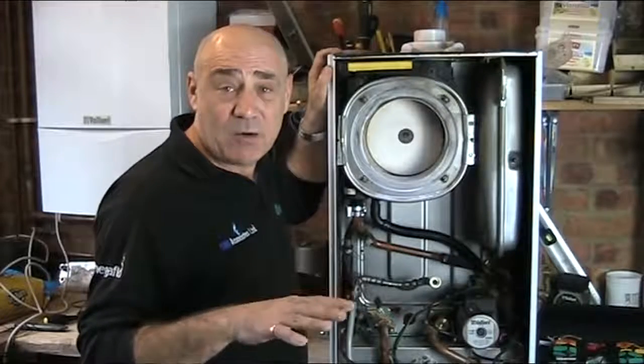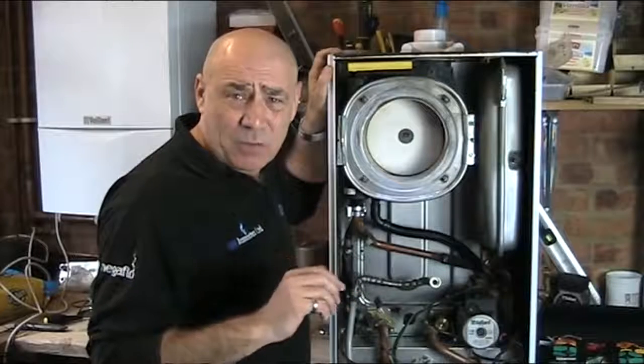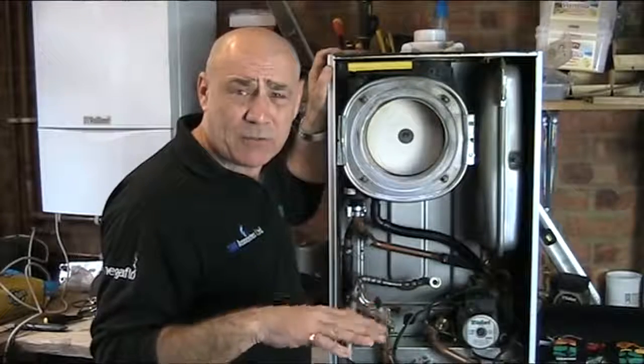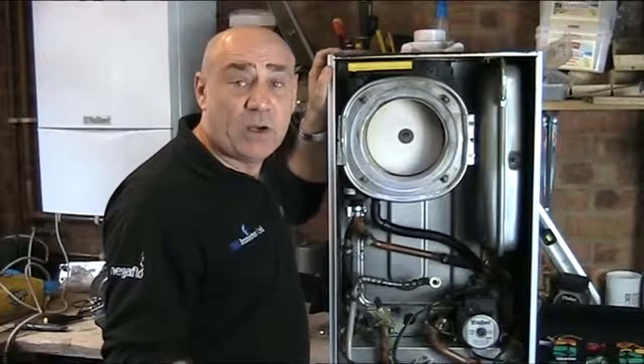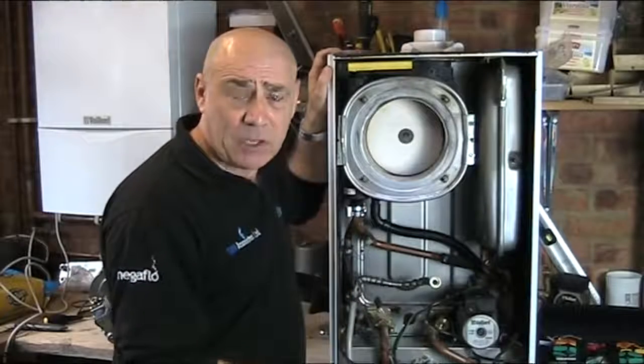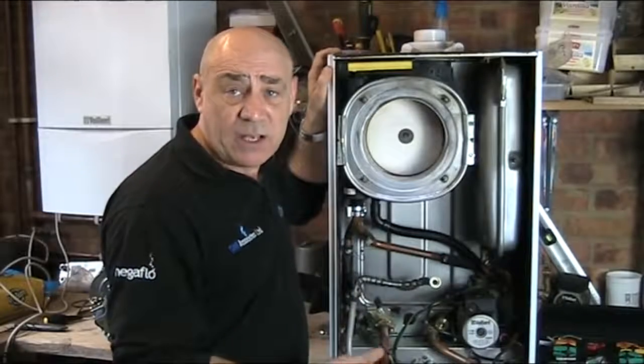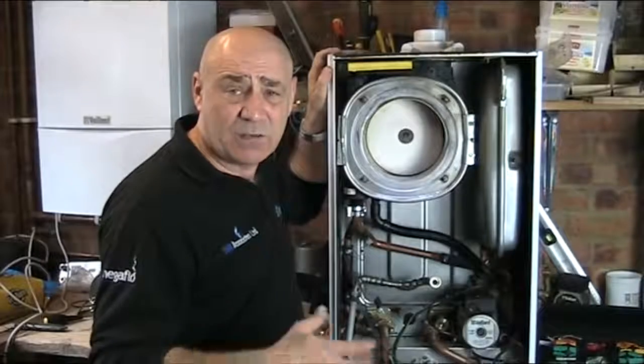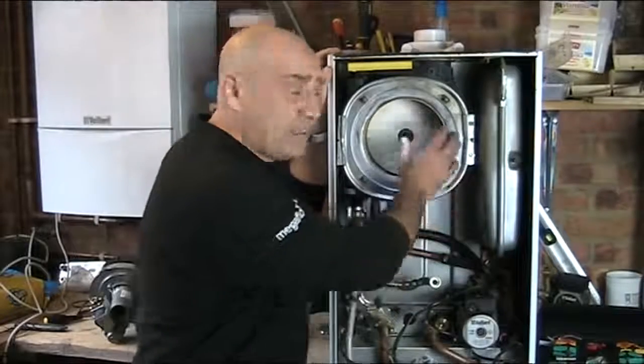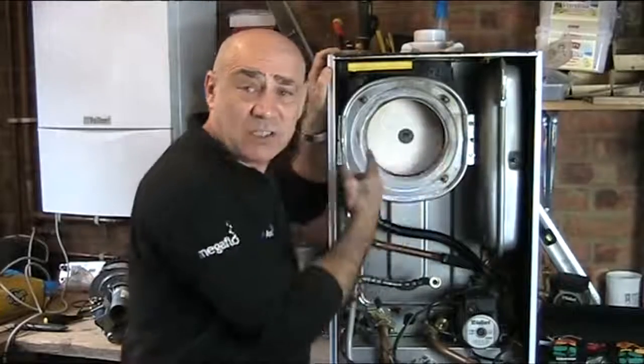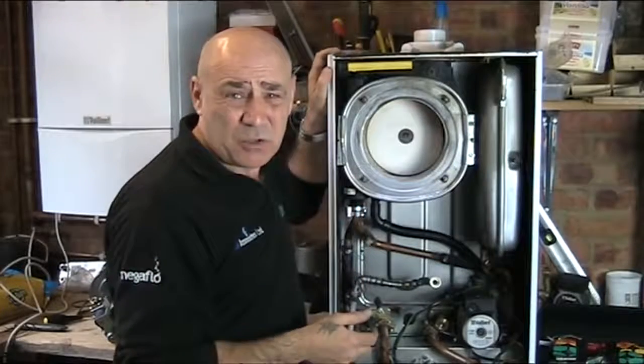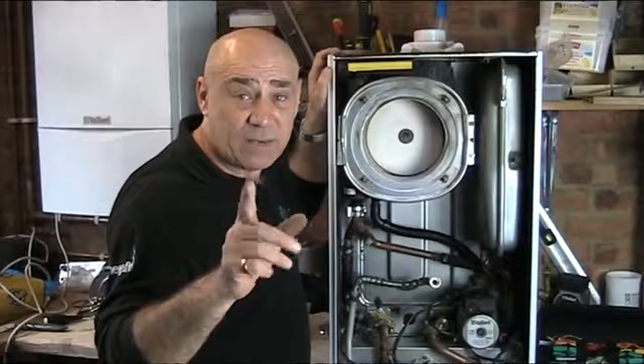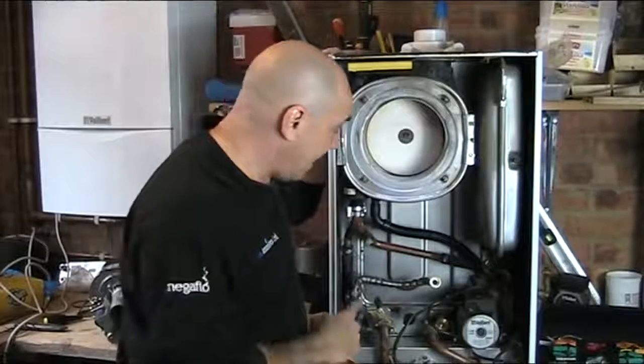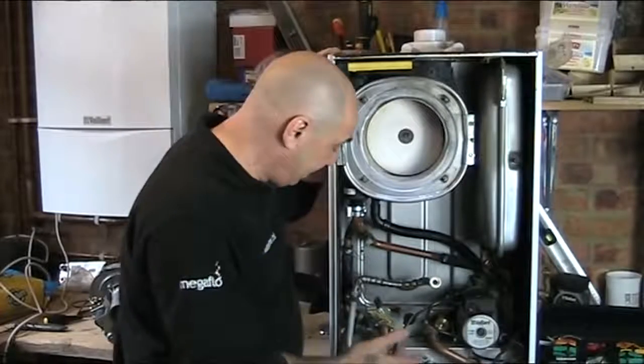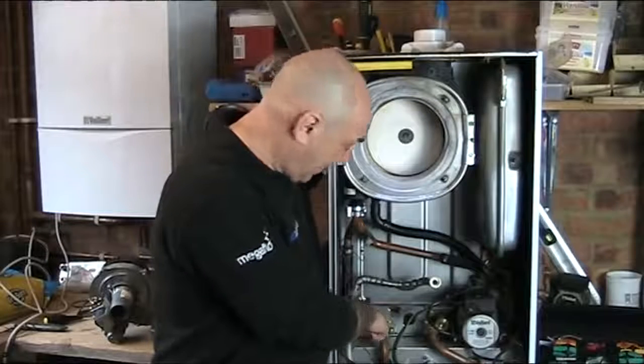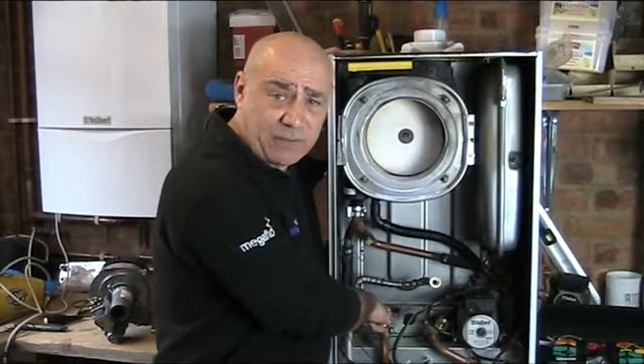And if the chemical level seems to be borderline, or perhaps a little bit low in your heating system, we will then inject a top-up dose on that service, so it maintains the cleanliness of your heating system to protect this heat exchanger, because if that gets blocked up, you might as well write the boiler off. Very, very important.